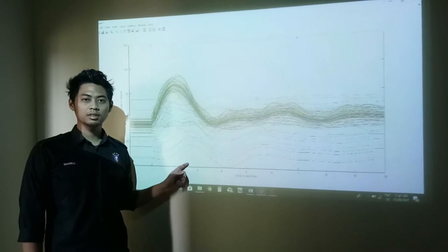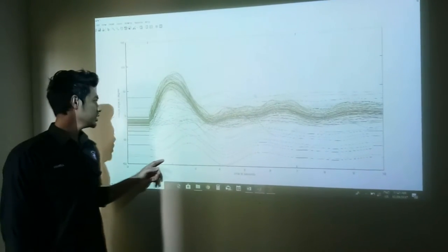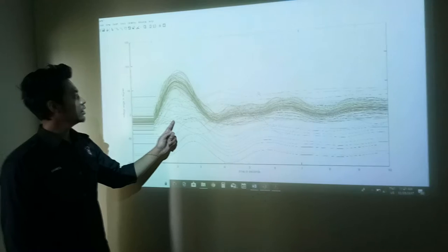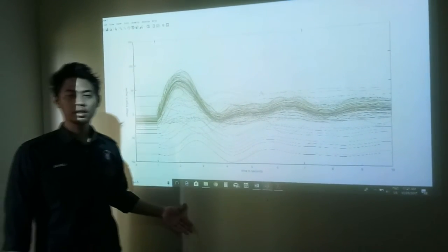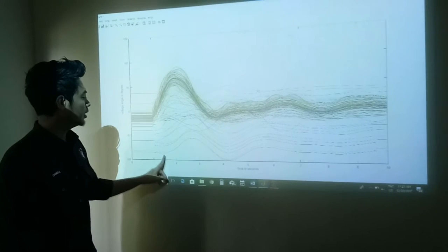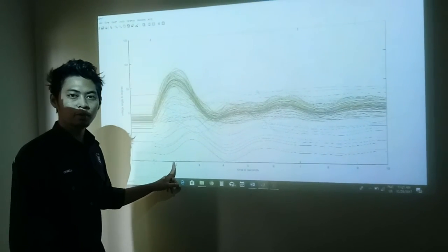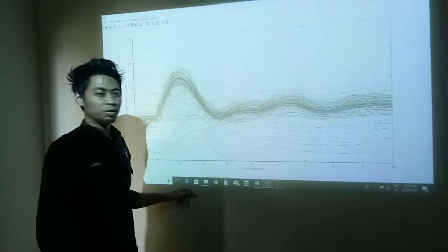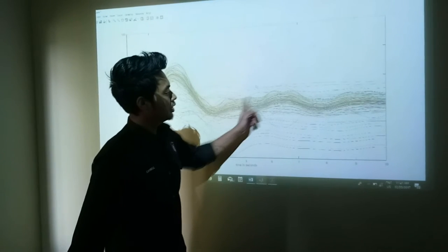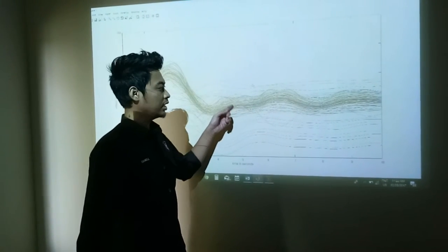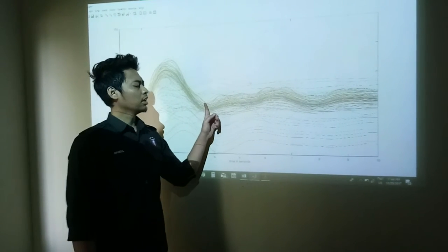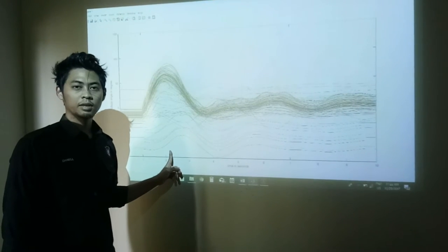And lastly, for our result in the stable case studies, we get the result for the voltage angle in degrees. For the peak angle, we get 100 degrees against time, which means after the 1.16 clearance, the graph will also go to a stable condition. Here we can see all generators represented in the graph. They go to a stable condition after we clear the fault in the network system.